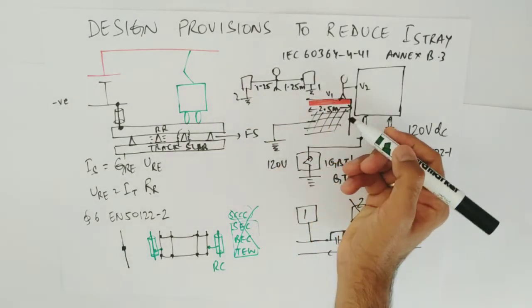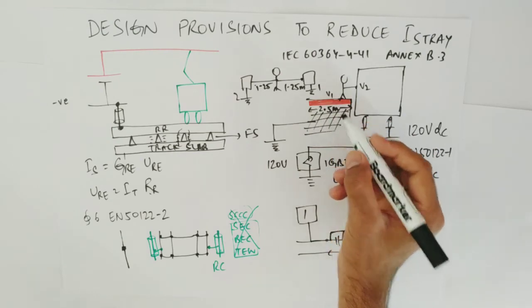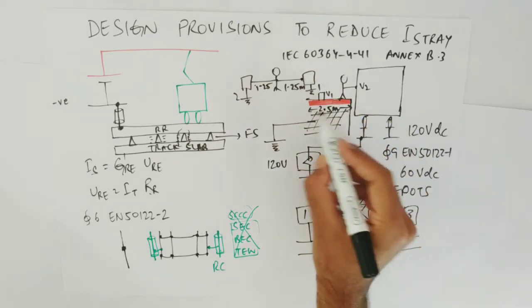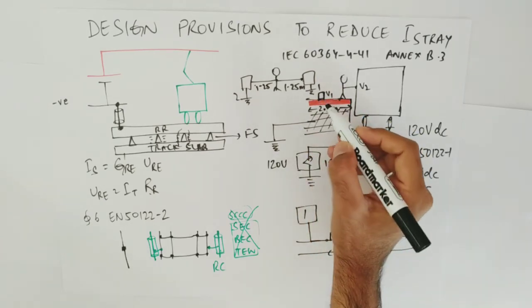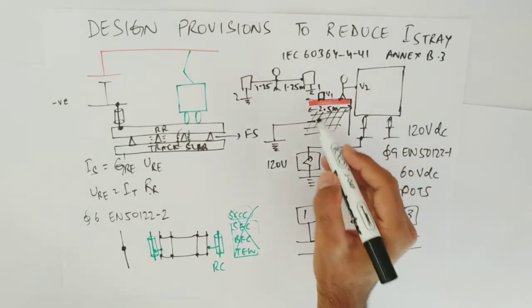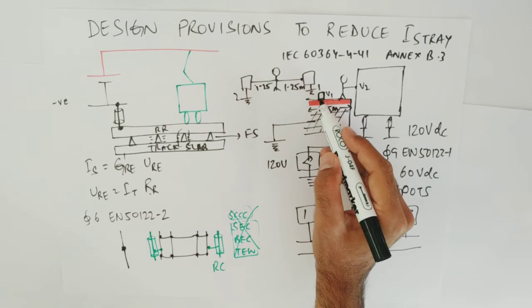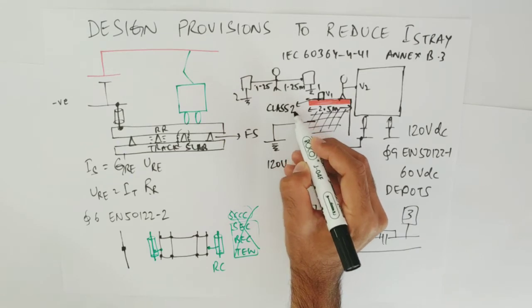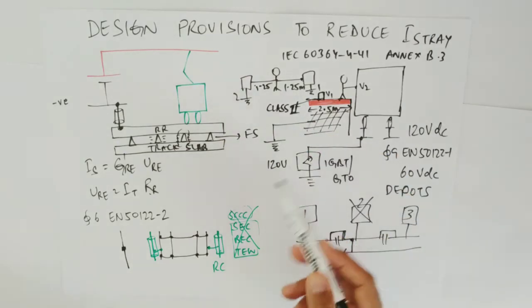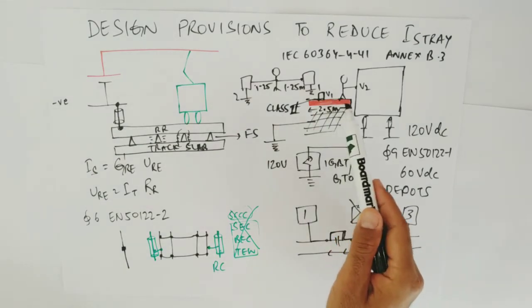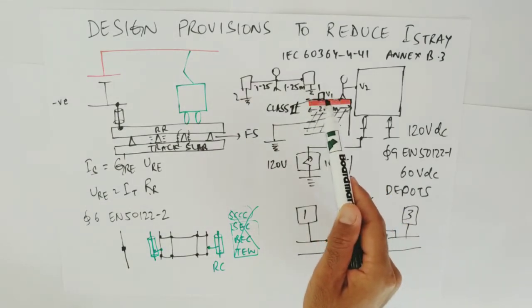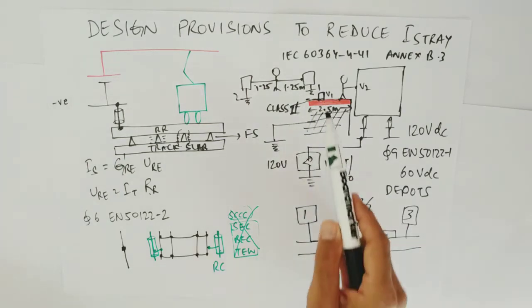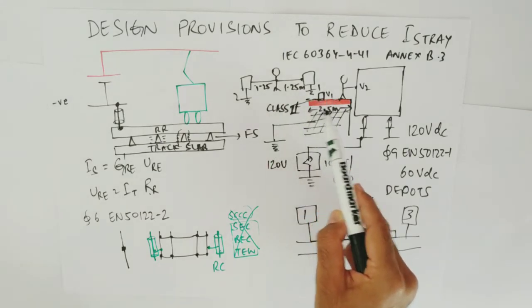Apart from the membrane, there shall be no equipment within this 2.5-meter region. If it is mandatory to place any equipment there, it shall operate at extra low voltage and shall have Class 2 insulation. There shall be no earth conductor from the station coming into this region.